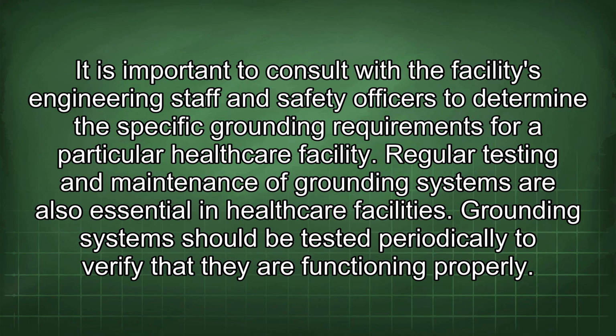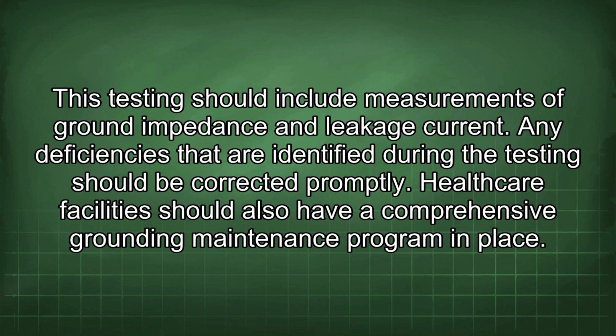Regular testing and maintenance of grounding systems are also essential in healthcare facilities. Grounding systems should be tested periodically to verify that they are functioning properly. This testing should include measurements of ground impedance and leakage current. Any deficiencies that are identified during the testing should be corrected promptly.